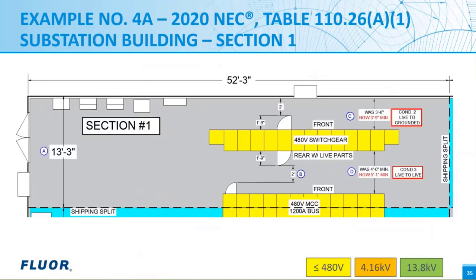Here in section one, we see two increases in the required workspaces. The dimension near bubble C on the upper right of the slide was 3 foot 6 inches, and now it is going to increase to 3 foot 9 inches due to the new requirement.